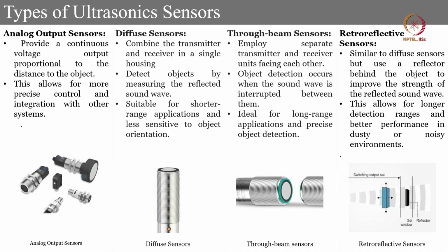The first one, analog output sensors, provides a continuous voltage output proportional to the distance of the object. This allows for more precise control and integration with other systems. The diffuse sensors work on the principle of combining the transmitter and receiver into a single housing. It can detect objects by measuring the reflected sound wave. It is suitable for short range applications and less sensitive to object orientation. The through beam sensors employ a separate transmitter and a receiver. As you can see, one is transmitter, one is receiver, T or R, R or T.